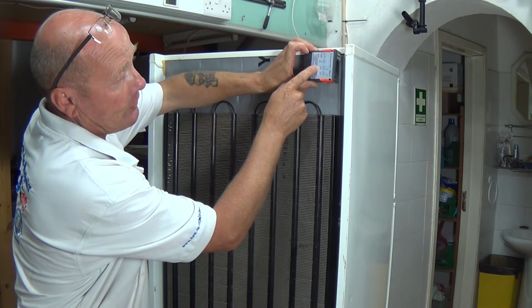Basically I'm going to run a live and neutral up to the relay or thermostat, and I'm going to link across on the live to the relay for the cooling side, and then take a wire from here down to the compressor for it to start the compressor.